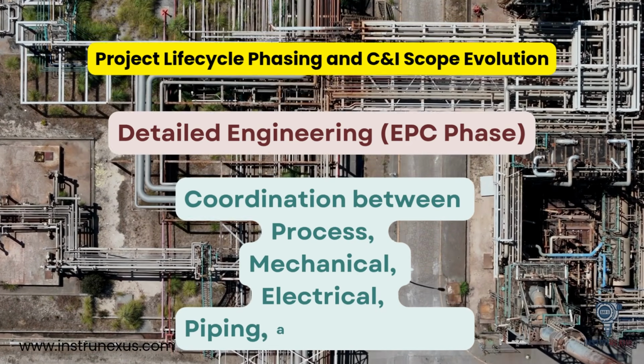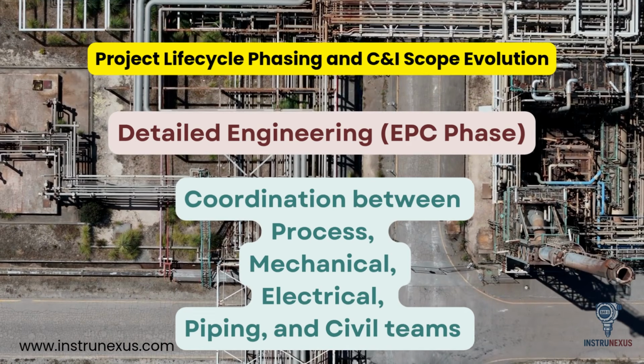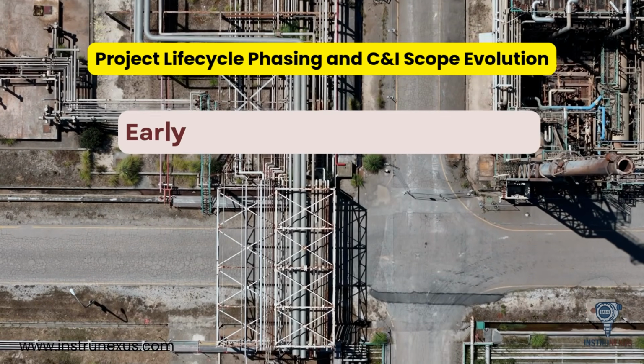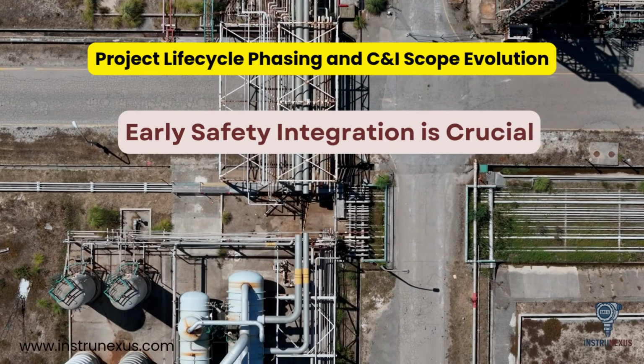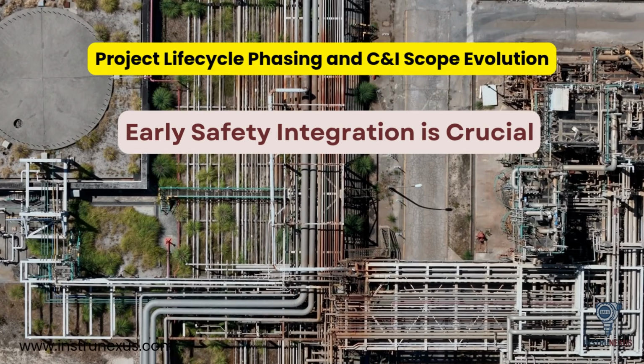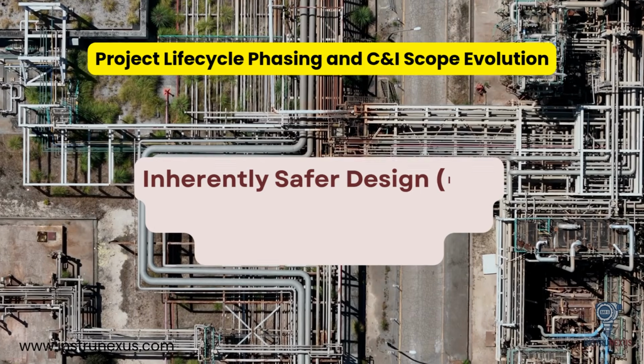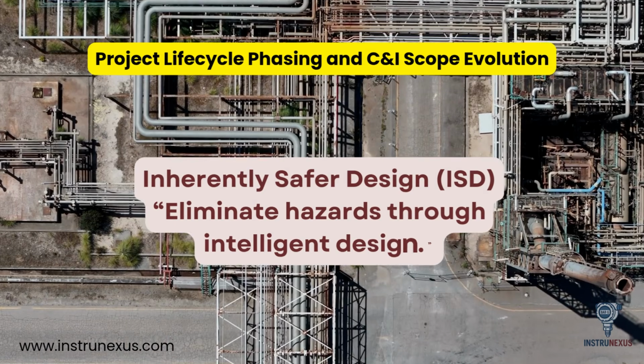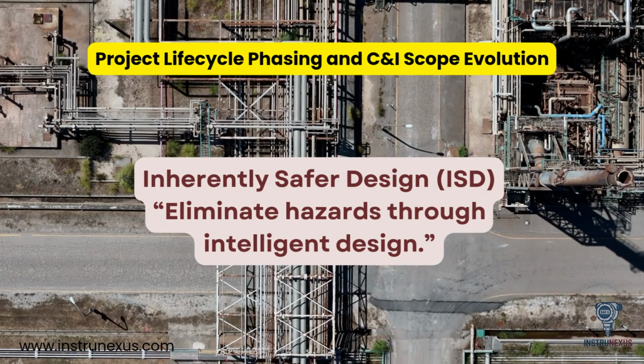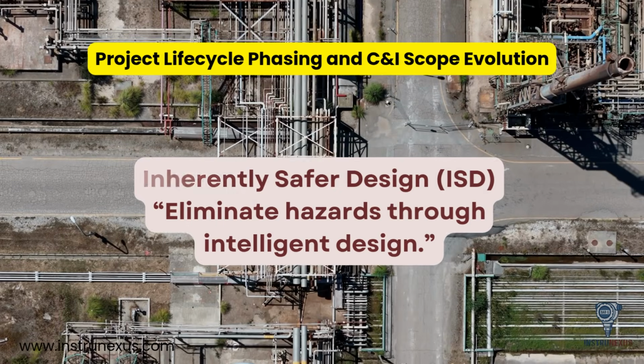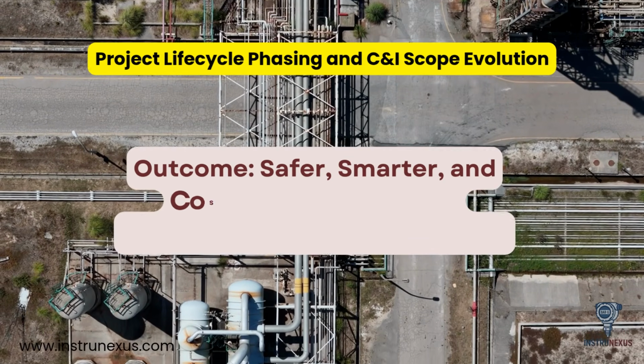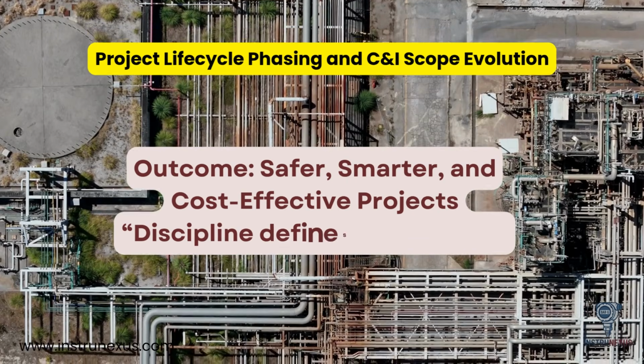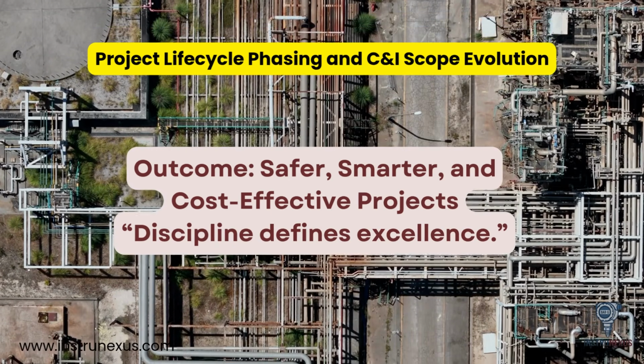A critical lesson across all phases: safety must begin early. When functional safety requirements under ISA 84 and IEC 61511 are delayed until detailed design, costly redesigns often follow. Instead, by integrating inherently safer design principles from the conceptual and FEED stages, engineers can eliminate hazards at their source, like designing systems that physically prevent overpressure or minimizing hazardous waste streams. Early safety integration saves time, cost, and effort, and defines the true value of disciplined C&I engineering.